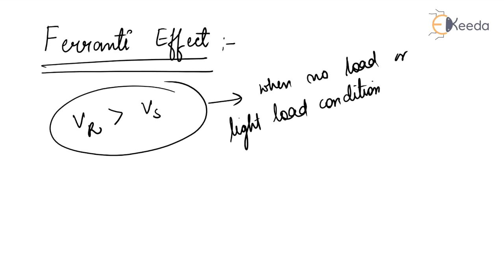This effect mainly occurs because of light load or open circuit at the receiving end. When a no-load or light-load condition occurs, the terminal voltage in a transmission line will be greater than the supply voltage, meaning Vr is greater than Vs. The Ferranti Effect is due to the charging current of the line.